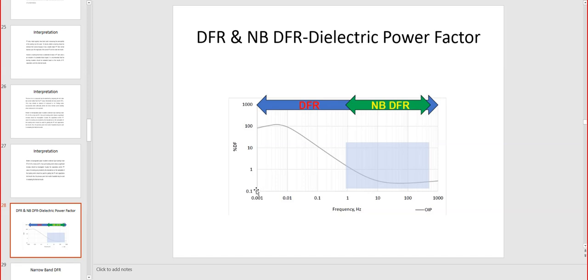So from 0.001 to 1000, we perform the same power factor test, applying those voltages that we talked about, but now we change the frequency. So the voltage, as you remember, depending on the manufacturer, can only be up to 2000 volts for G, and then Ohio Brass you have 250 and 500, and all the others are 500 AC, but it is not 60 hertz here. Actually 60 will be somewhere here between 10 and 100, right? So that will be the area where we read at 60, which is one point on this graph.